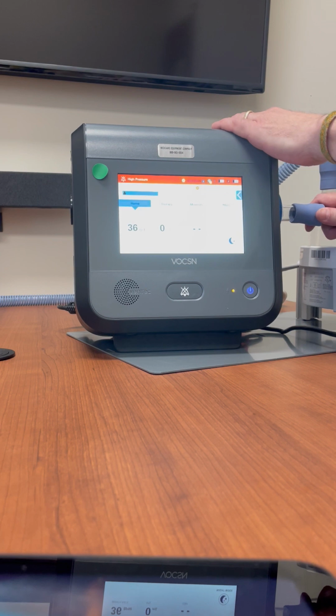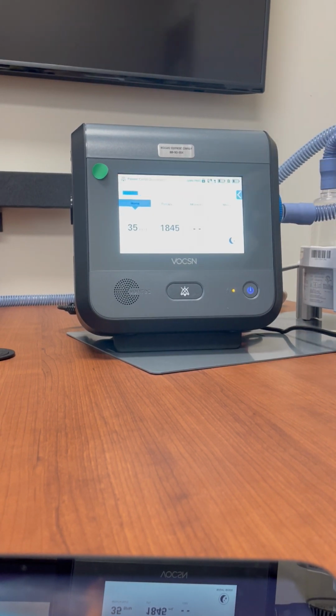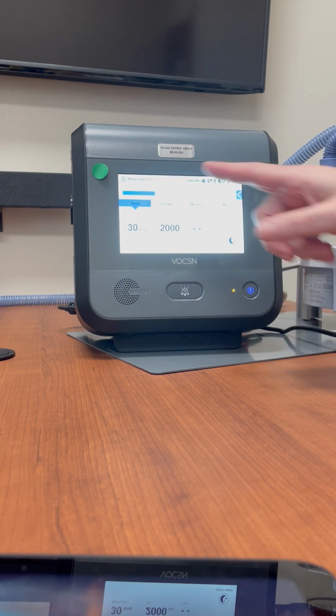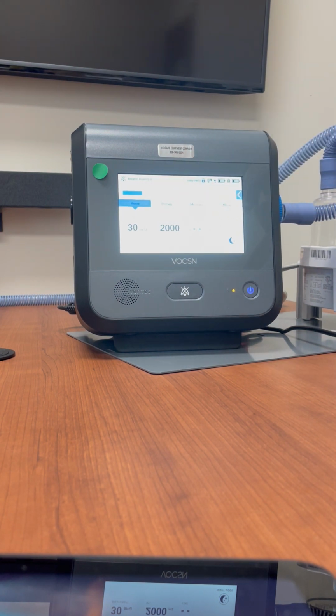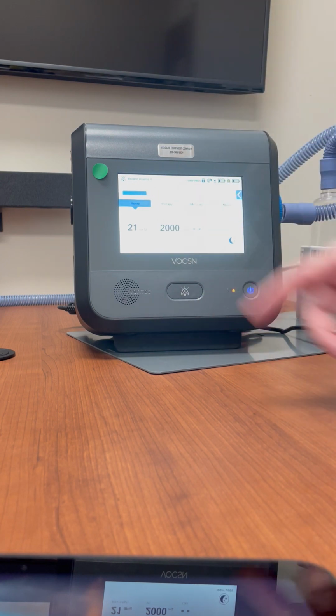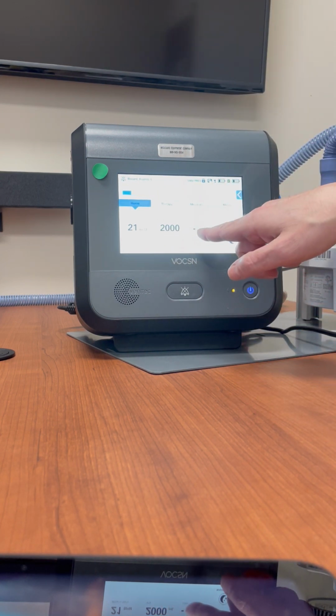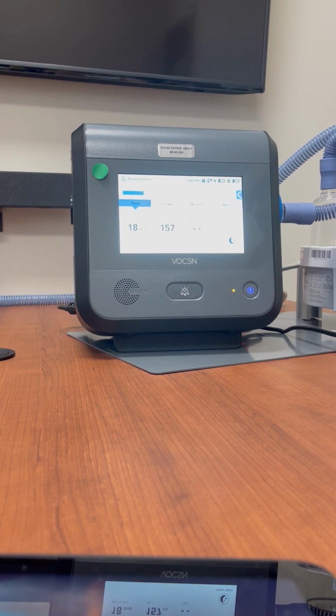Well, for us, I'm completely disconnected. So once I connect back up, the machine takes a few breaths and will recognize that there's no more leak anymore. And the alarm status bar is back to gray. Again, it takes a couple seconds to recalibrate, and we'll get a regular tidal volume and a normal leak again. For patients at home, this usually happens when the mask is too loose. It is leaking, a high leak in the 70s, 80s, 90s. So when you hear the patient disconnect alarm, automatically think about snugging the mask up on the patient's face.